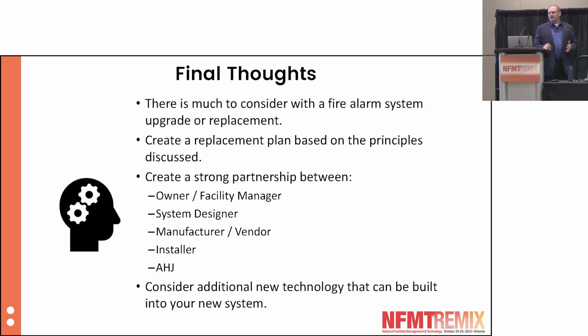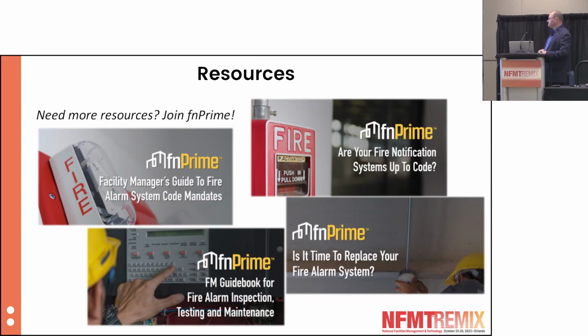And consider new technology that can be built into your system—addressable smoke detectors that can test themselves. That's really cool, but only one manufacturer has it. Addressable notification appliances that can test themselves—thousands of horn strobes and strobes can be tested in a matter of seconds, but again, only one manufacturer has that. So what's important to you? What new technology do you need to be building in? Because the best use of funds is always going to be a combination of these kinds of things to consider.